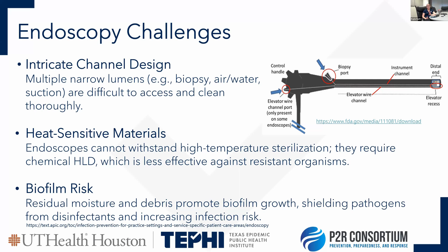Due to the multiple channels and not having direct visualization, they are dark, warm channels, which can have residual moisture, and we know warm, dark, moist items are breeding grounds for bacteria. They love to grow in them, and the development of biofilm can shield them from disinfectant and increase infection risk for these devices. Another thing is that they can also undergo microscopic damage. Sometimes with these scopes the tips can get bent, broken, or cracked, and it's really hard to see, so you might not know it's defective. Also, with the internal lumen, you might not know it's cracked in there because you don't have direct visualization, as I mentioned.